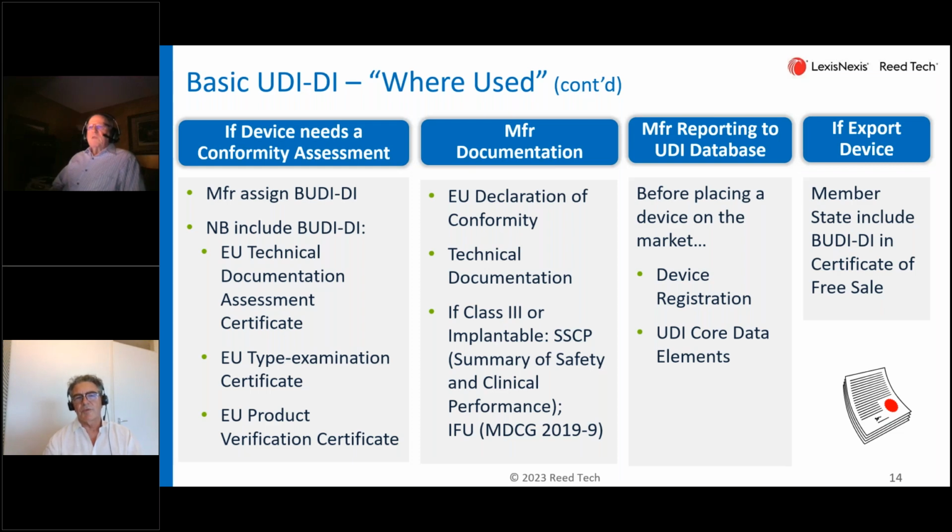Yeah, when your device needs to be certified, whether it's self-certified or notified body certified, you need to assign your Basic UDI early on. So then you have grouped your device. That's what I strongly recommend. If you haven't started doing it, start doing it tomorrow or today even, depending on your time zone.